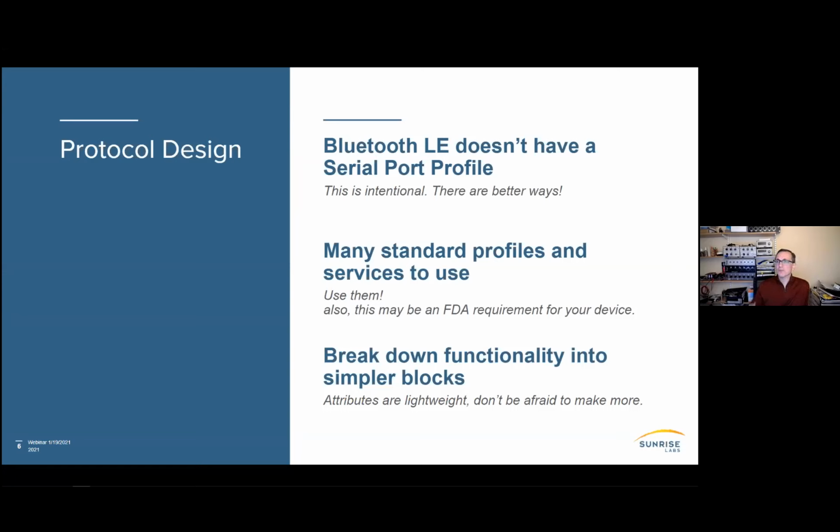In fact, it's impossible to make an 11073 compliant BLE link. You can make it compliant through the application layer, but not through the device layer, or the communications layer. And so the guidance was to follow and use the standard profiles whenever there is one available.